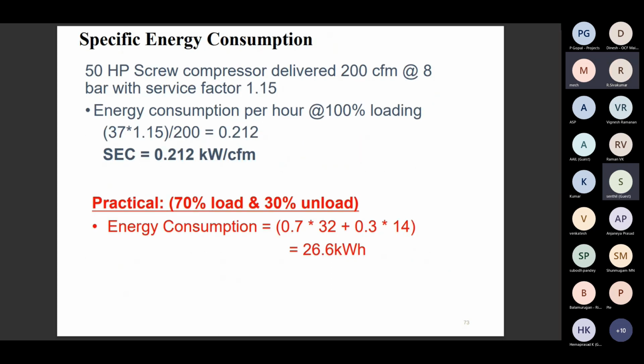So, specific energy consumption. For the 50 HP screw compressor delivering 200 CFM at 8 bar with a service factor of 1.15. Normally the compressor manufacturer says the service factor is 1.15, 1.2, sometimes 1.25. Based on that, the energy consumption per hour is 37 kilowatt, because 50 HP is nothing but 37 kilowatt. 37 into the service factor of 1.15 divided by 200 CFM means the specific energy consumption is 0.212 kilowatt per CFM.